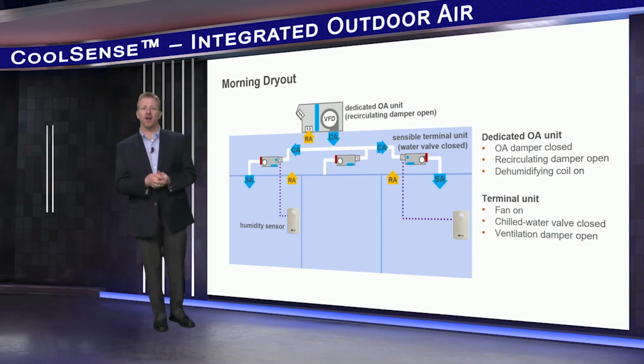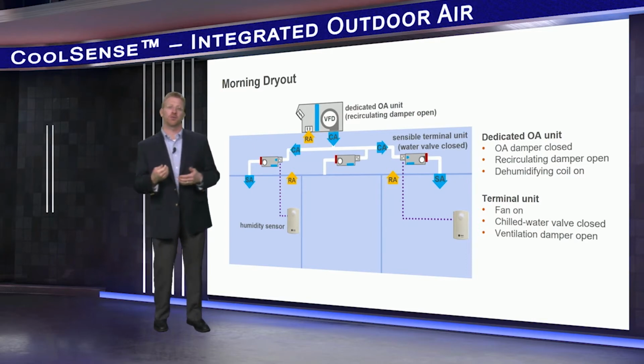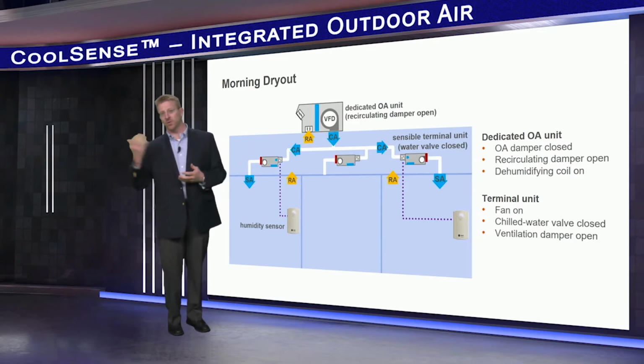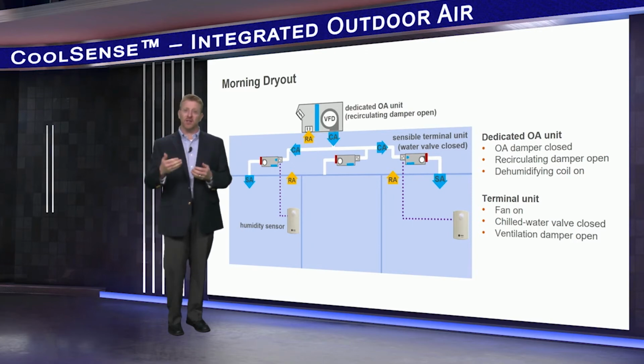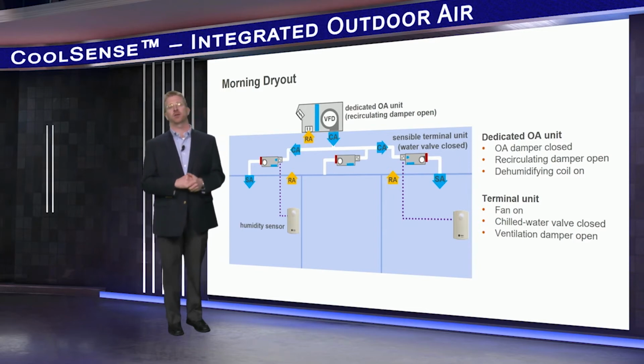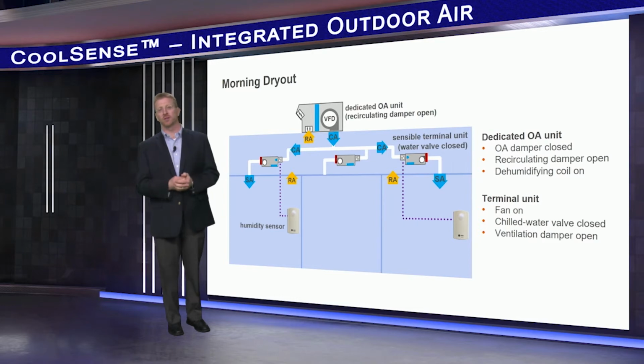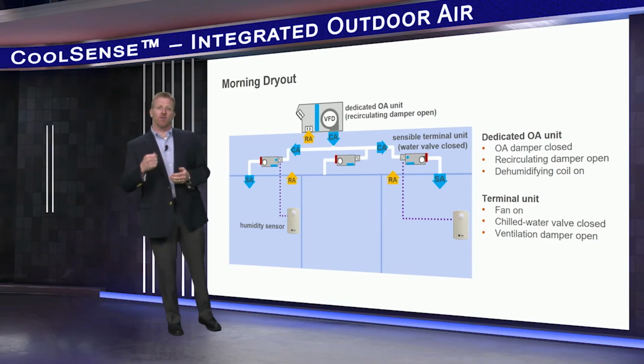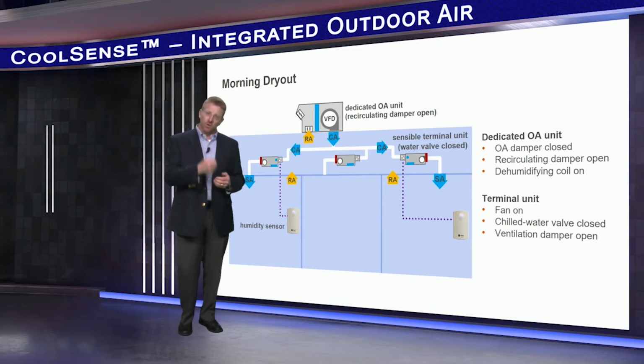When the building is unoccupied, we typically let the temperature drift to save money. In the winter, we let it get colder. In the summer, we let it get warmer. Then we proactively set a time when the system needs to start such that the building is back to set point when it's time to occupy the space. No big deal, and it's easily understood. However, for sensible cooling systems like CoolSense, we have spoken about the need to control the dew point in the space also.